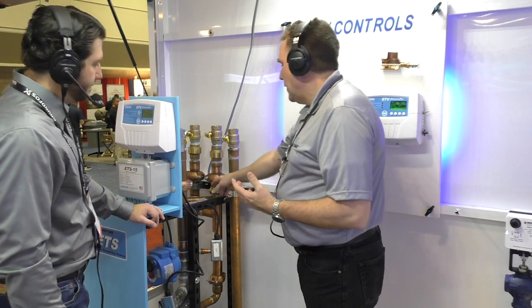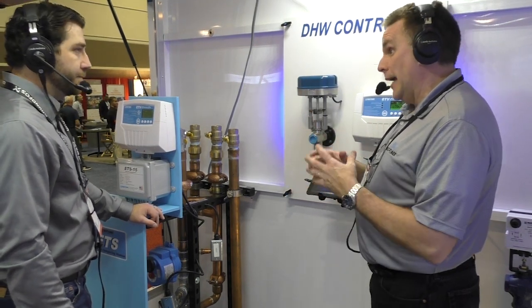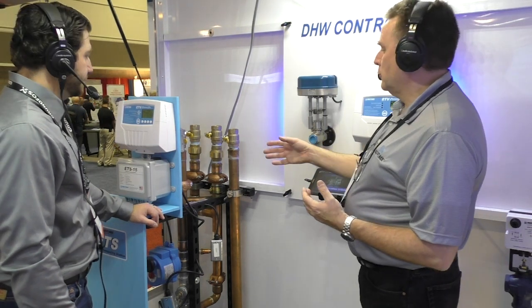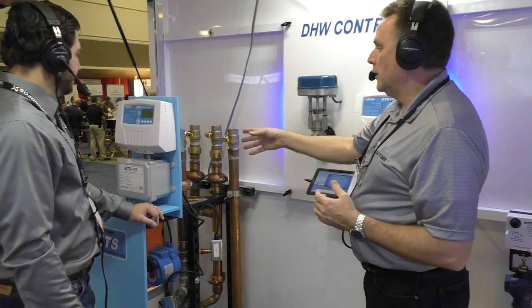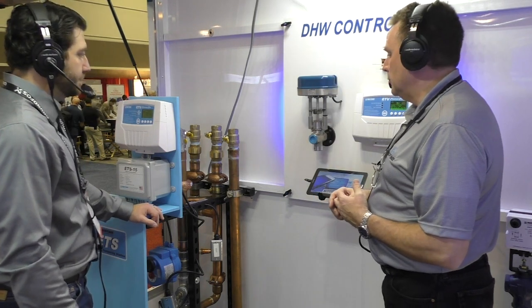Every ETS has 5 connections to it. So you'll see there'll be the cold water supply coming in from the street. We have the building recirc coming in. And then what we do is we have what we call the magic T. That's where we bring the recirc in prior to where the cold water would split off, going to the ETV valve and then to the water heaters. That T is very critical because that gives us recirc to both the heaters and to the valve, and it will naturally balance itself. So that's one of our connections, which is the cold recirc going back to the water heaters. We have the connection for the hot coming from the water heaters, and then, of course, we've got the mix going out to the system.